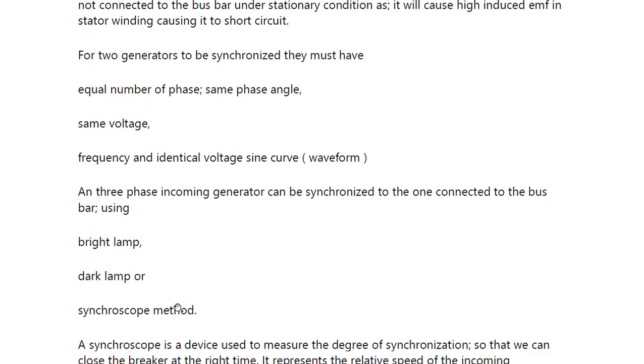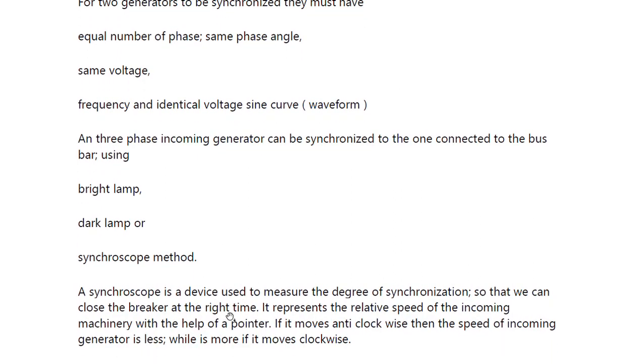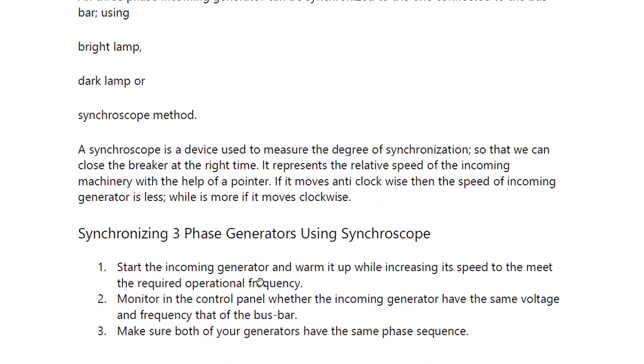A three-phase incoming generator can be synchronized to the one connected to the bus bar using the bright lamp, dark lamp, or synchroscope method. A synchroscope is a device — you may have seen it on the panel on ships — it has dots arranged in a circle like a watch face. It is used to measure the degree of synchronization so we can close the breaker at the right time, at 12 o'clock. It represents the relative speed of the incoming machinery using a pointer. If the pointer moves anti-clockwise, the speed of the incoming generator is less; it must always move clockwise.